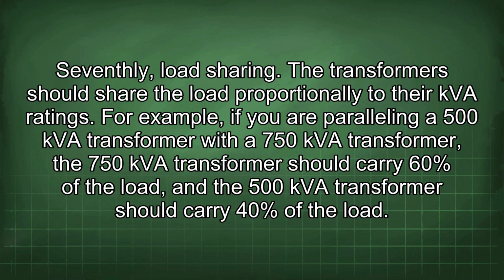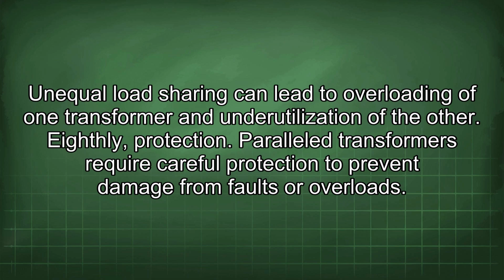Seventhly, load sharing. The transformers should share the load proportionally to their kVA ratings. For example, if you are paralleling a 500 kVA transformer with a 750 kVA transformer, the 750 kVA transformer should carry 60% of the load, and the 500 kVA transformer should carry 40% of the load. Unequal load sharing can lead to overloading of one transformer and underutilization of the other.